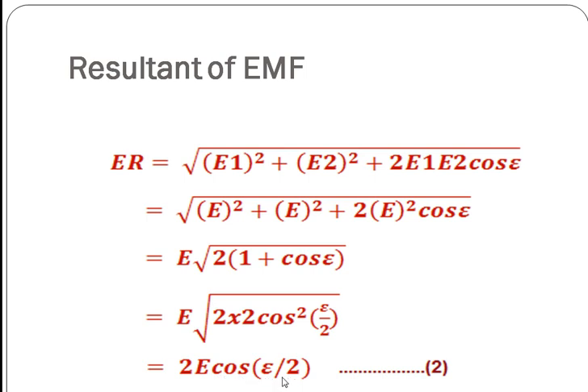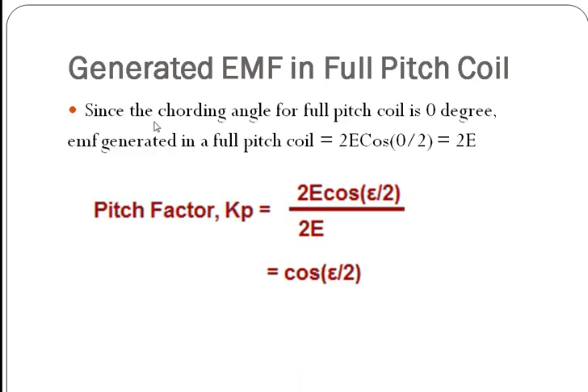If you solve this equation, you will get EMF available at the terminals of the short pitch coil to be equal to 2E cos(zeta/2). Now let us calculate the EMF generated in a full pitch coil. The chording angle for a full pitch coil is equal to 0, so if we put 0 in place of zeta, the EMF generated in the full pitch coil will be equal to 2E cos(0/2), which equals 2E. According to the definition of pitch factor, Kp equals 2E cos(zeta/2) divided by 2E, which equals cos(zeta/2). Therefore, the formula for pitch factor is Kp = cos(zeta/2).